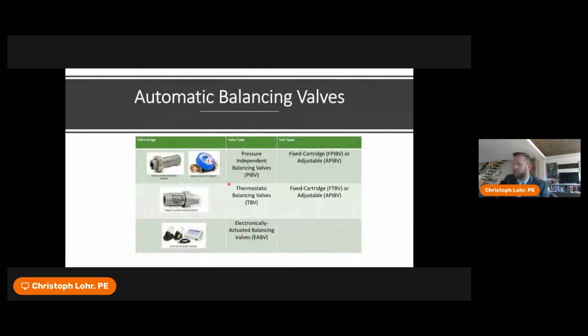What much of the industry is moving towards is automatic balancing valves, of which there are 3 types: pressure independent balancing valves, thermostatic balancing valves, and electronically actuated balancing valves. For pressure independent and thermostatic balancing valves, there's 2 types: fixed cartridge or adjustable types. Electronic offer the opportunity to do all the balancing electronically.